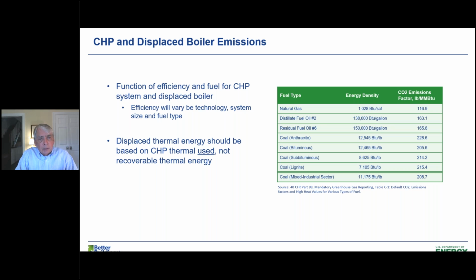One key thing to remember is that for estimating the displaced emissions and fuel for the boiler, only the thermal energy that is actually used can be counted. Sometimes you can recover more thermal energy from the CHP system than you actually use on site, so you have to base the calculation on what's used on site.